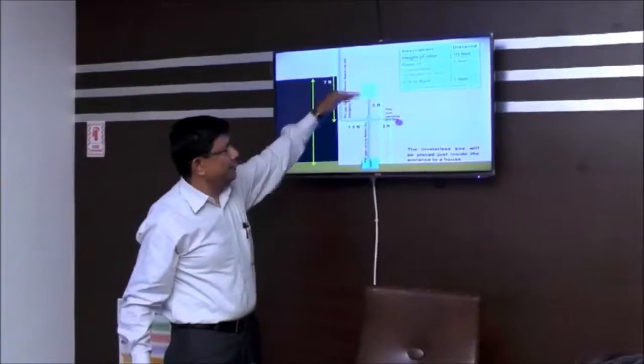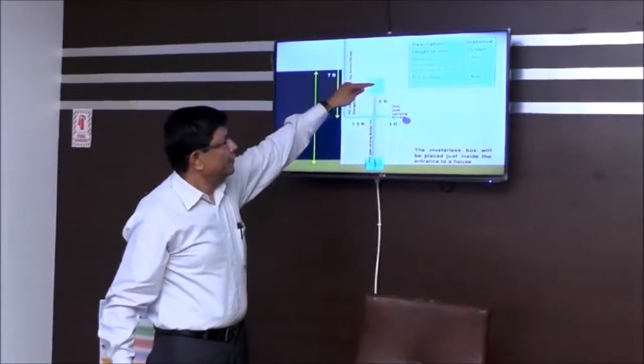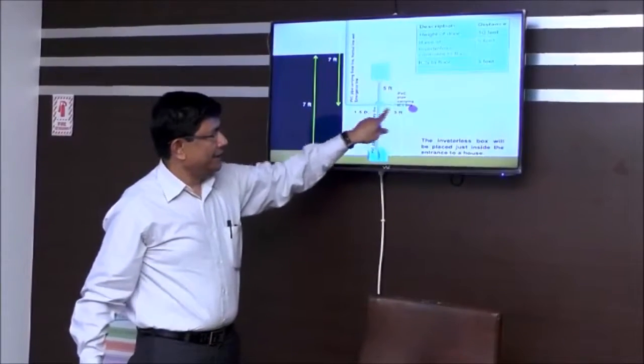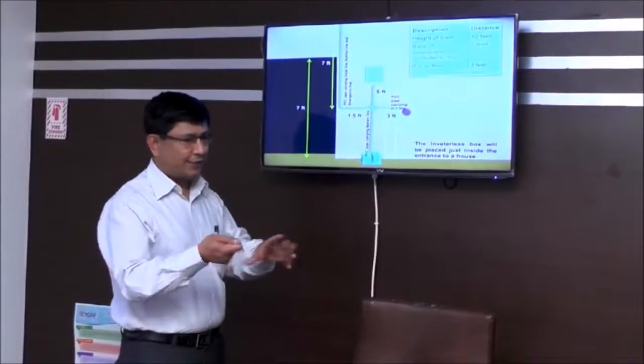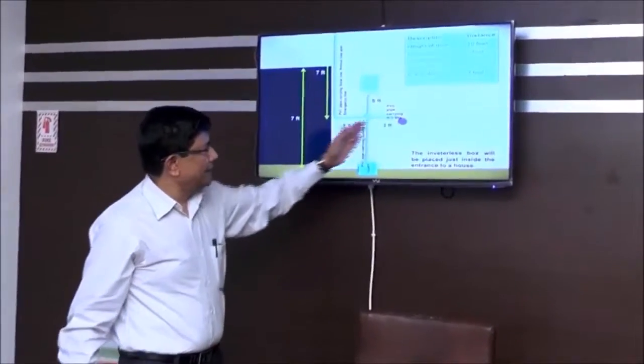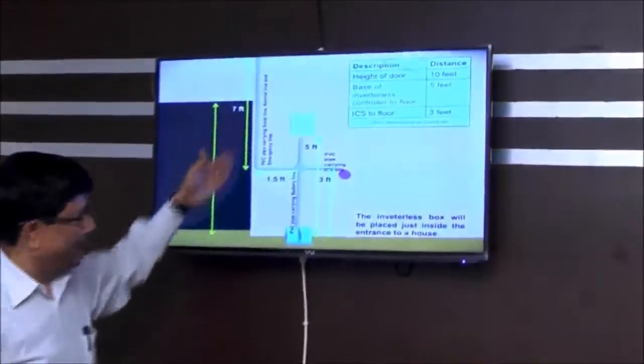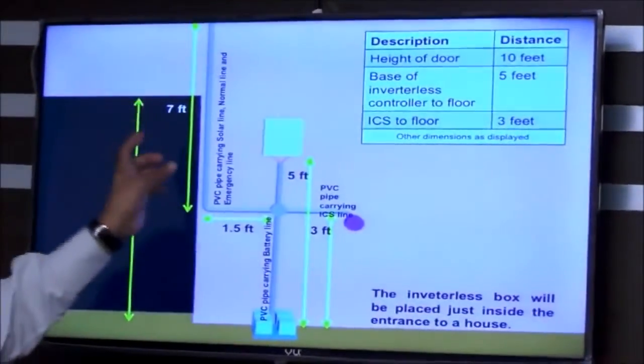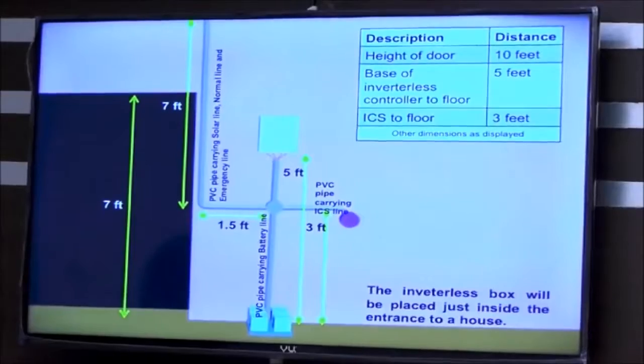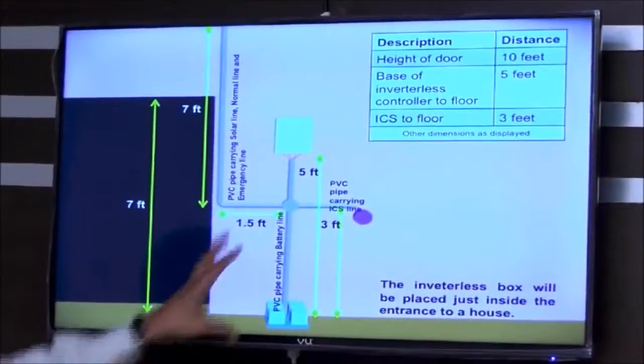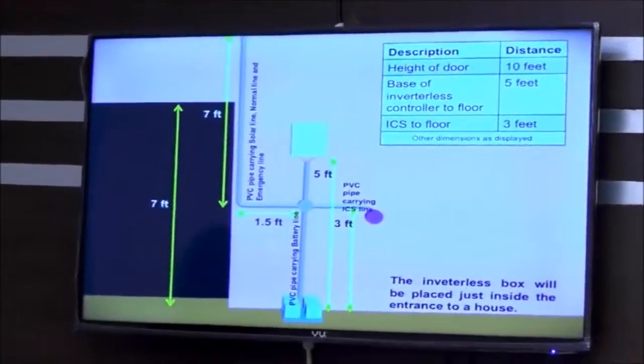What we have done is the inverter box is about five feet from the ground so that you can look at all the LED indications. The mobile charger is at about three feet so that you can charge your mobile phones from there. This whole distance is about one and a half feet from the edge of that wall. You take this wiring along the edge of the wall so that you provide a clamp and everything there. If you do this, then you will have an approximate idea in terms of how much cable is required.